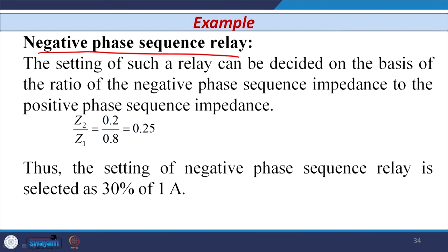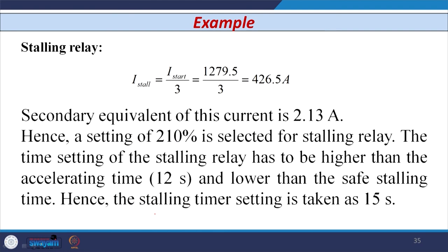For the negative phase sequence relay setting, the ratio of negative sequence impedance to positive sequence impedance is used: Z2/Z1 = 20%/80% = 0.25, or 25% in percentage. The setting range of the negative phase sequence relay should be greater than 25% of 1 A, so we can consider 30% of 1 A as the setting of the negative phase sequence relay.